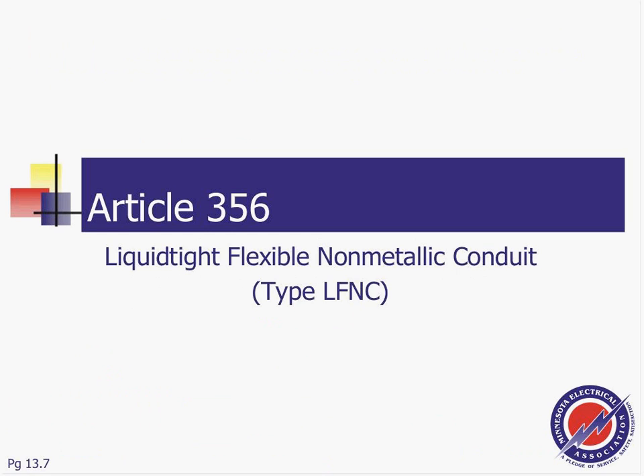Very interesting to read this when it comes to using it as an equipment grounding conductor. It's different. There are different amps and different requirements for it. Still to be listed. Anything, guys, about the grounding? So that's basically for Liquidtight flexible metallic conduit. We talked about the grounding and the requirements for the grounding, support, and so on. Marking, it has to be marked. So that's basically it in terms of that.